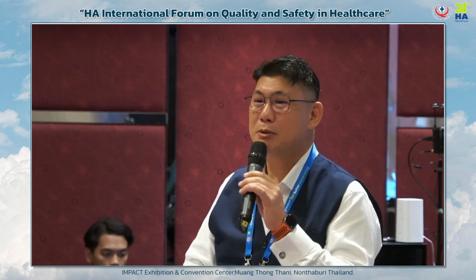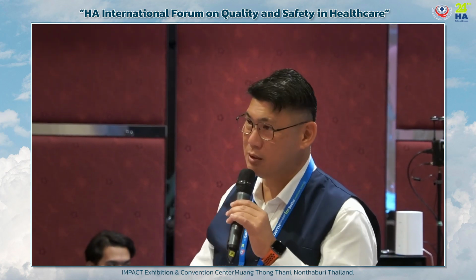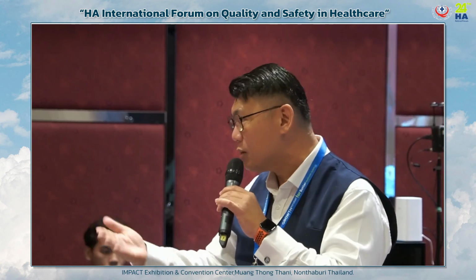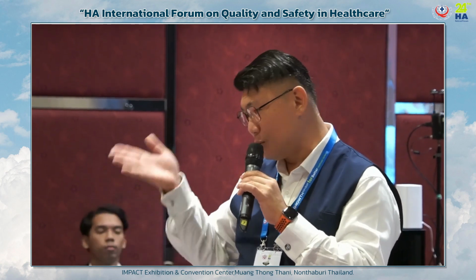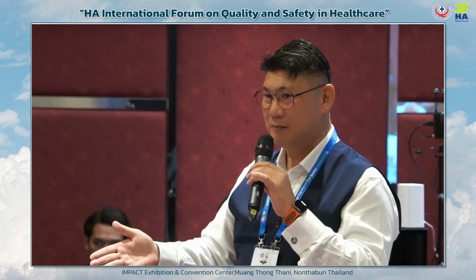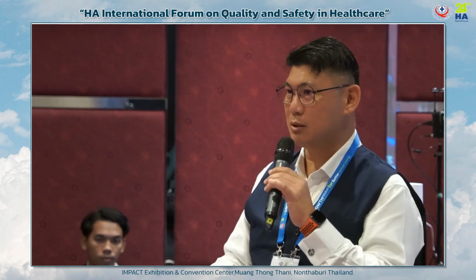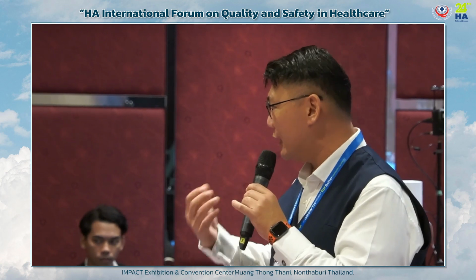That's what maybe you do every day, especially with your POC. Be careful with your POC equipment, point of care analyzer. Be very careful. Need to clean it. POC also needs cleaning. You don't just, with no maintenance, it will give you wrong result. Then at POC, wow, high glucose, then you start to diagnose the patient wrongly again. Many of these instances have happened.